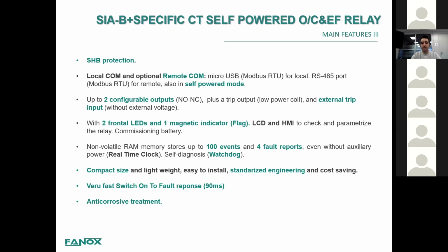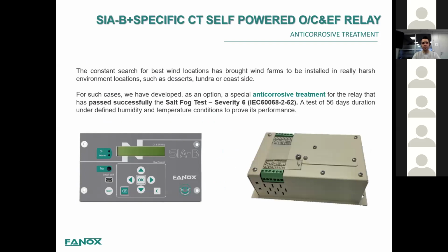We also have an anti-corrosive treatment on this relay. As you know, renewable wind farms or solar farms are being located in different and unusual places: deserts, tundra, close to the coast. This implies that our relays need a higher degree of protection than the traditional ones in the substation. That's why we developed, in coordination with some of our customers, a relay that has successfully passed the salt fog test with severity 6 according to the IEC standard. It's a test lasting 56 days, with defined characteristics of humidity and temperature. Our relay has been tested and passed, so it is completely approved to work in these harsher environments.